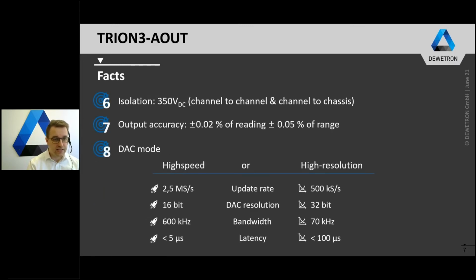So further facts, the channels are isolated with 350 volt DC channel to channel and channel to chassis, and the output accuracy is an astonishing 0.02% of reading.